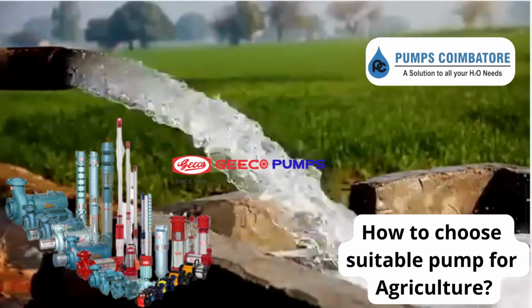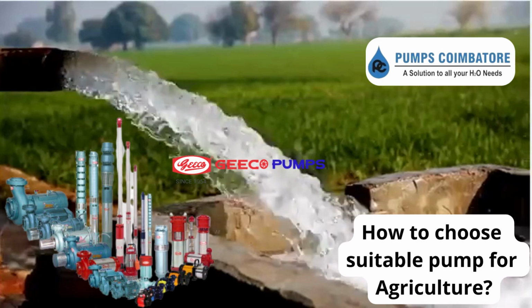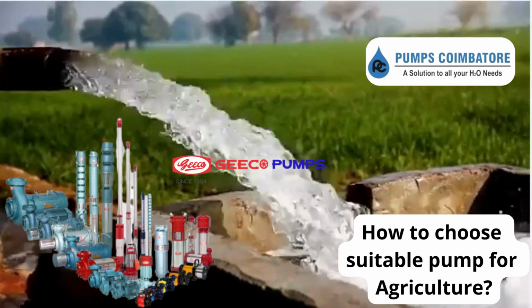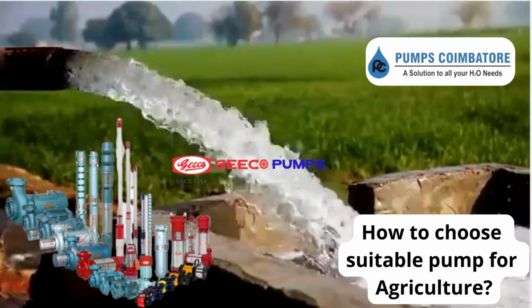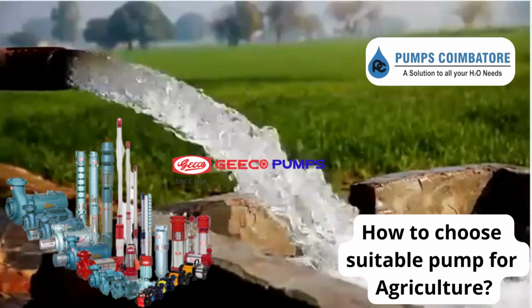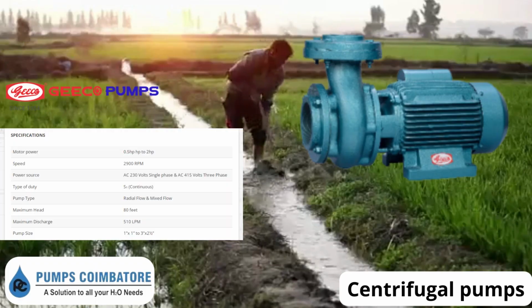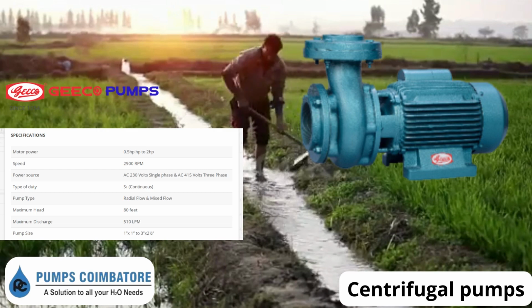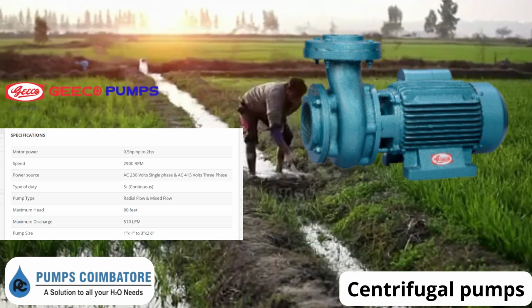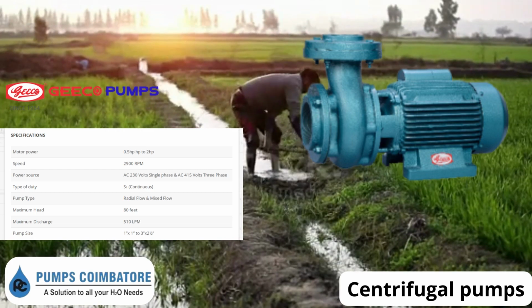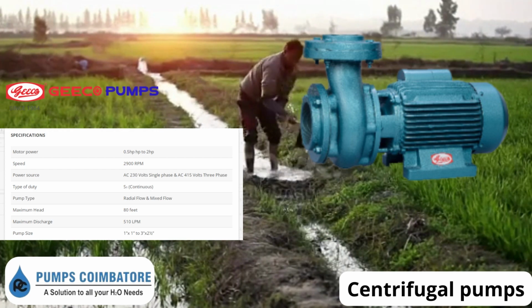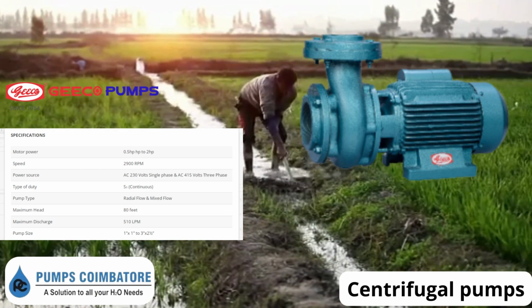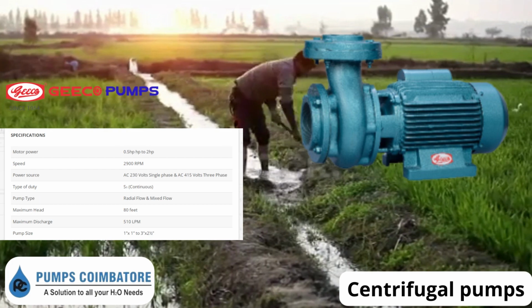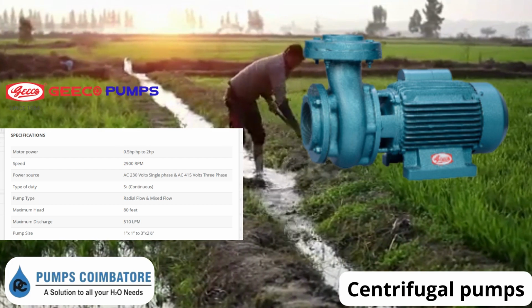When selecting an irrigation pump, consider the pump's operating conditions including the type of water source, the required pumping flow rate, total suction head, and total dynamic head. Surface water or well water will give you the source of water, and its availability will be determined by the local geology and hydrologic conditions. The type of irrigation system, the distance from the water source and the size of the piping system will determine the flow rate and total dynamic head.